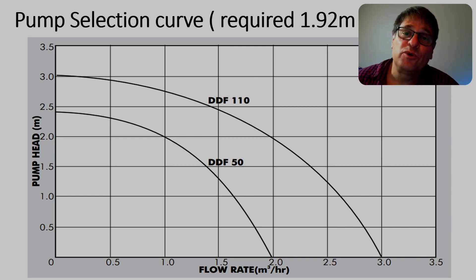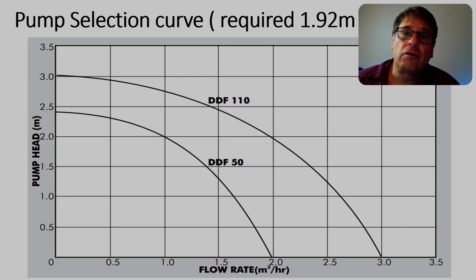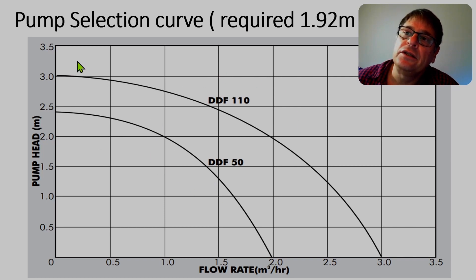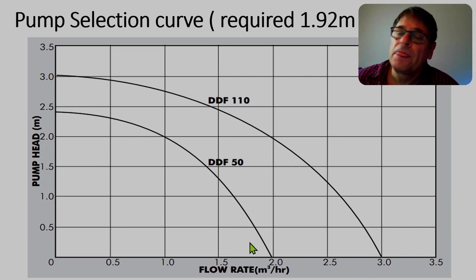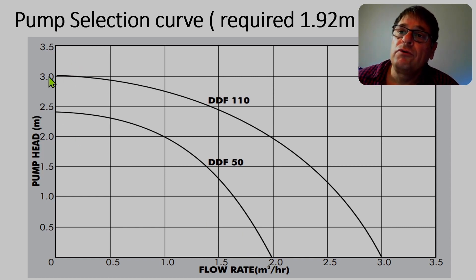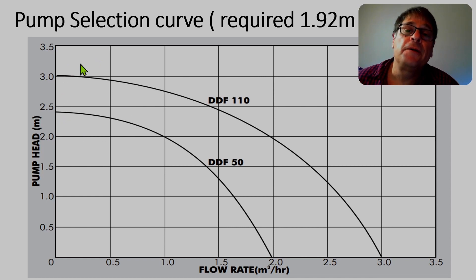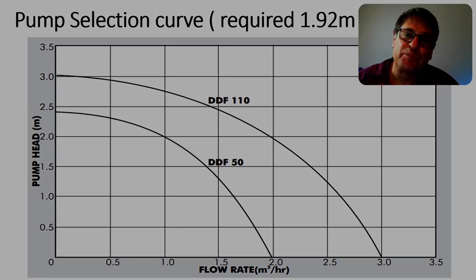Another tip is that pumps are more efficient towards the center of the curve. So in that central area, the pumps will be more efficient than at either end. If your calculated results fall within a less efficient area, it will be better to look for another pump.